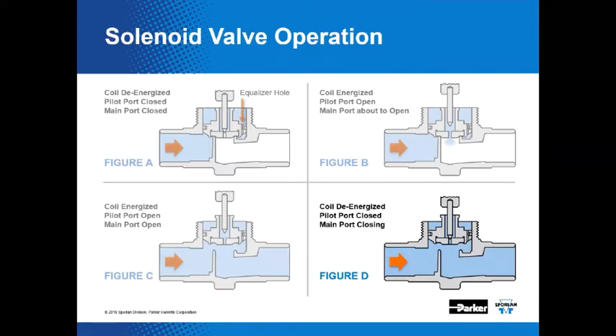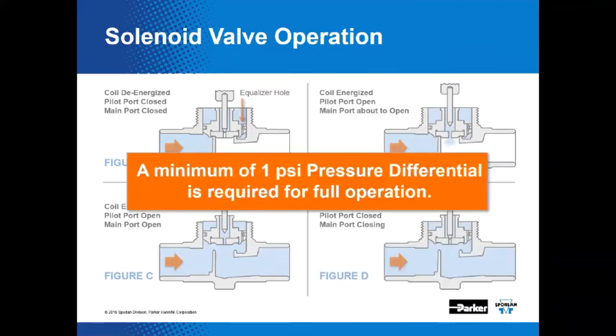Phase four: when we want to shut off the valve, we de-energize the solenoid coil. The plunger falls based on gravity or the kickoff spring. You're no longer venting pressure from above the seat, and as refrigerant continuously flows through the valve the pressure will build, allowing the seat to fall closed. Importantly, you must have a minimum of one PSI pressure differential for full operation. Without that differential, the valve will not stay open. This is why it's so important not to oversize solenoid valves — when they're oversized, you don't have a pressure drop, and these normally closed valves will stay open.